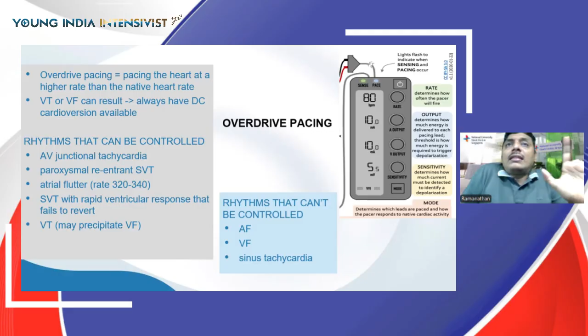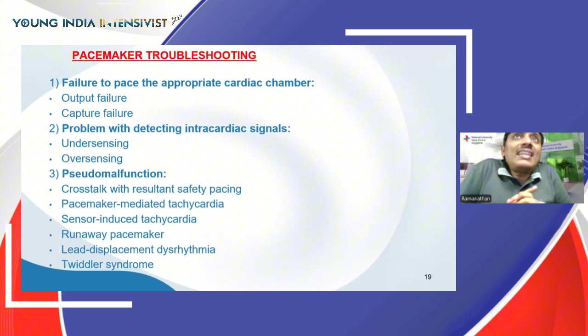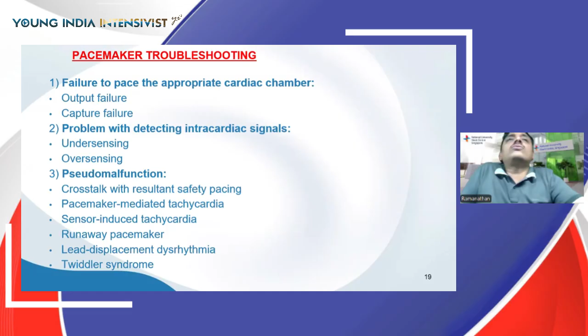Now, when you have a pacemaker with your patient and you are operating it, clearly you're going to come across some scenarios which will need some basic idea of how you troubleshoot it. So your pacemaker may fail to pace. Your pacemaker may fail to detect cardiac signals, so fail to sense, and there can be some pseudo malfunction which needs some tweaking here and there. Now, I'm not going to go through all these troubleshooting techniques, but two things you need to know would be how to manage them under general principles and how to manage failure to pace, failure to capture.